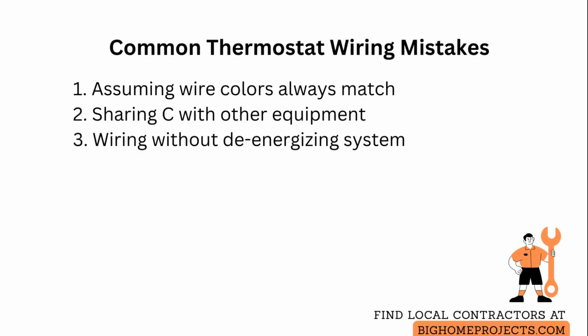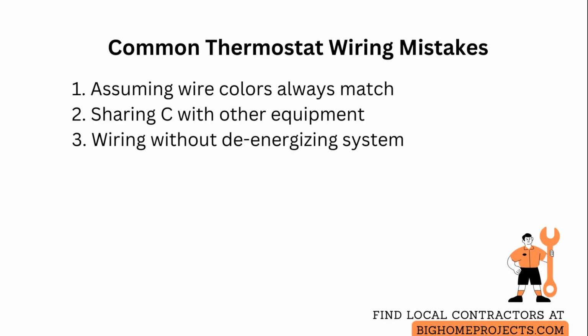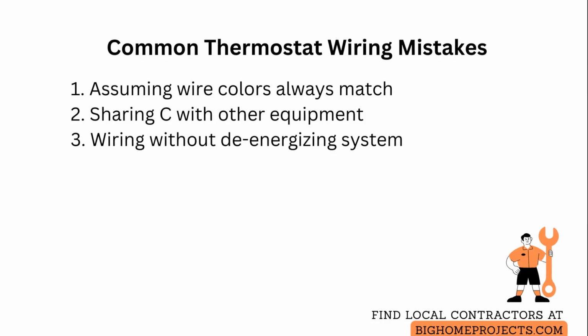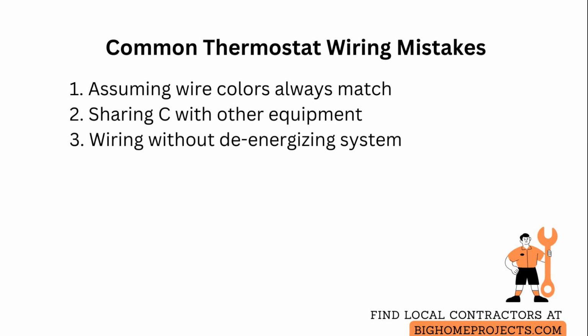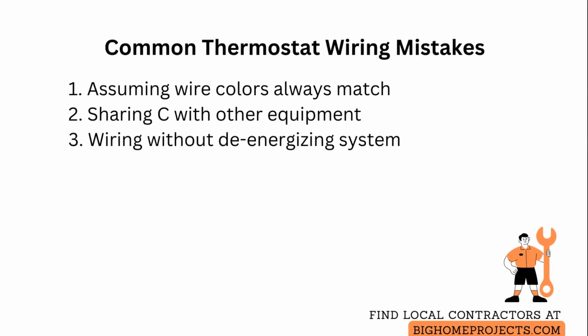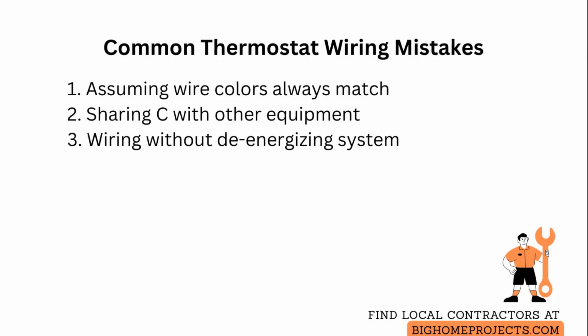Common mistakes include assuming wire colors always match the function, which can lead to connecting the wrong conductor. Always trace and confirm at the control board before attaching. Another issue is using improvised jumpers or sharing the C with other equipment, which can overload the transformer. If power demands are high, upgrade to a higher capacity transformer or run dedicated wiring.